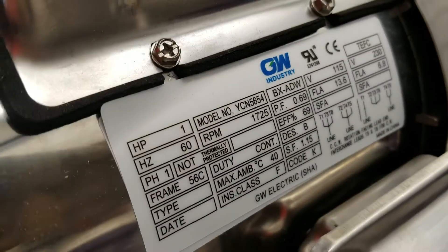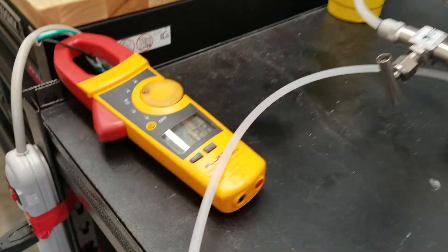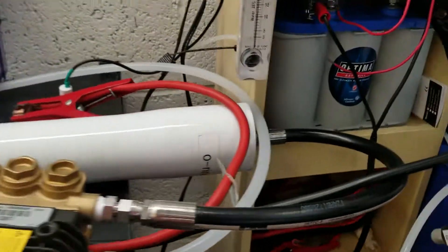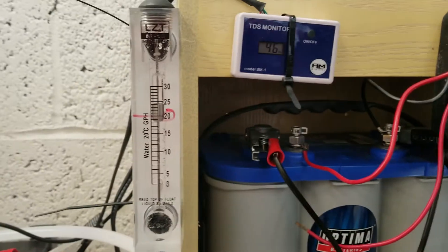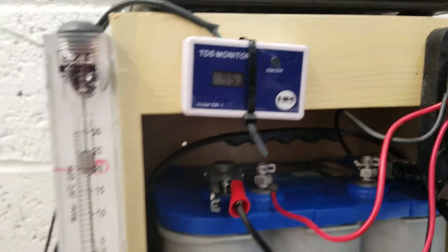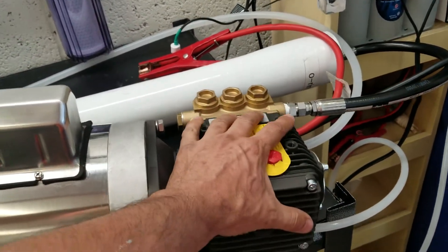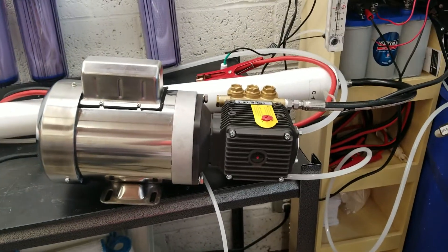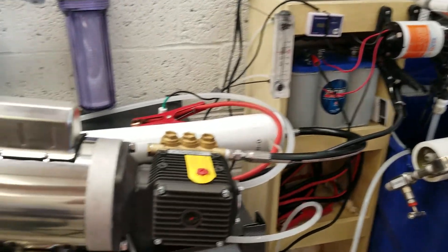Motor is rated for 13.6 amps and we are drawing 12.8 — what would you expect? We are exceeding spec on the production. That is great, very smooth and quiet. Thank you.